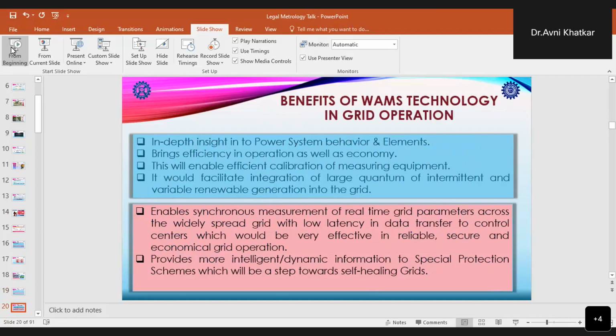Now, having this WAMS technology in the grid is very beneficial for grid operation because it provides in-depth insight into the power system behavior and elements. It brings efficiency in operation as well as in the economy, and it will also enable efficient calibration of all the measuring equipment. It will also facilitate integration of a large quantum of intermittent and variable renewable generation into the grid. And this also enables synchronous measurement of real-time grid parameters across the widely spread grid with lower latency in data transfer to control centers, which would be very effective in reliable, secure, and economical grid operation. And it also provides more intelligent and dynamic information to special protection schemes, which will be a step towards having self-healing grids.